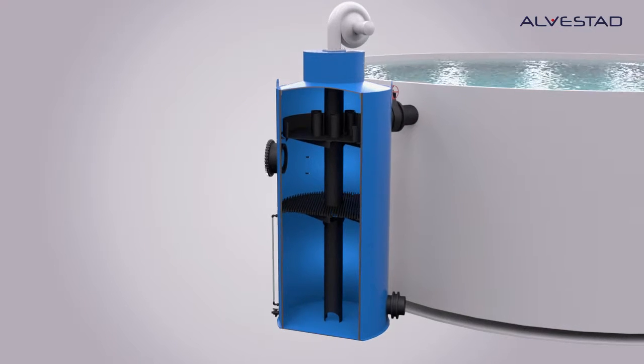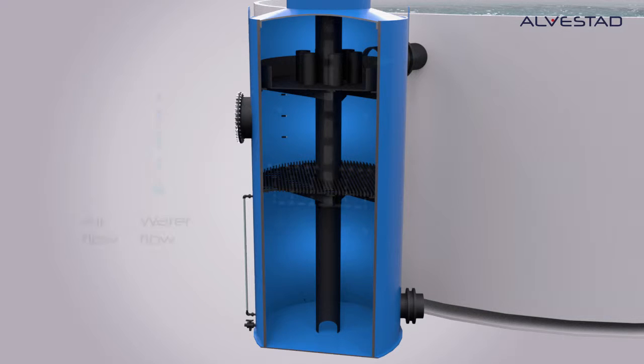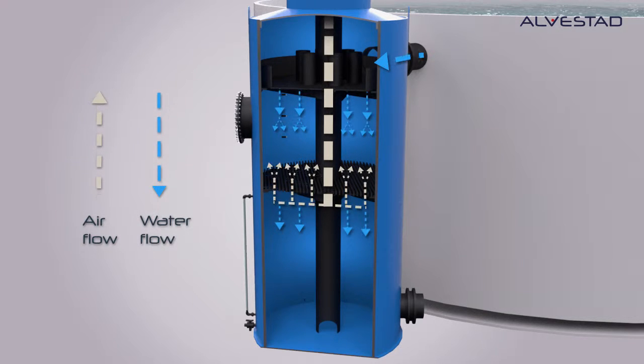The GasBuster aerator is built as a trickling column based on the counter-current aeration principle, which gives the highest efficiency for carbon dioxide removal. Water is evenly distributed at the top of the unit and, using gravity, trickles downwards through the aeration media.